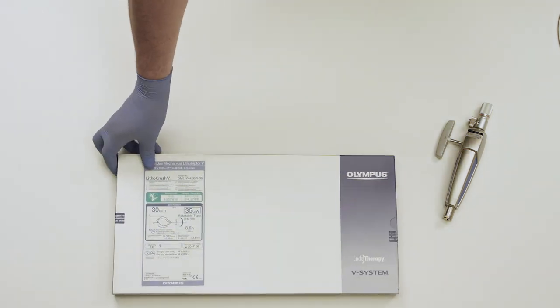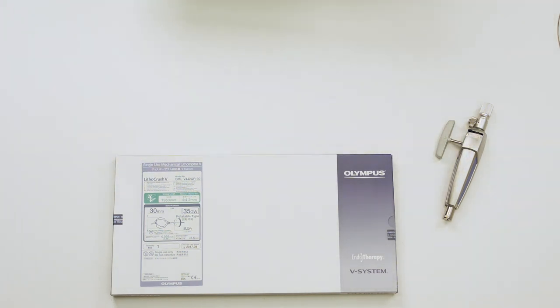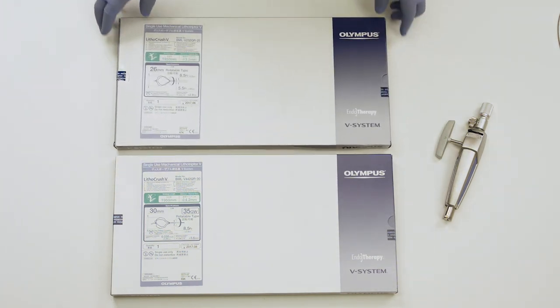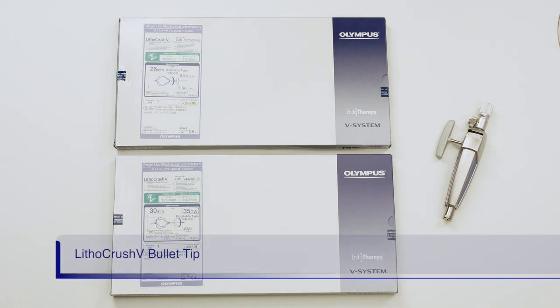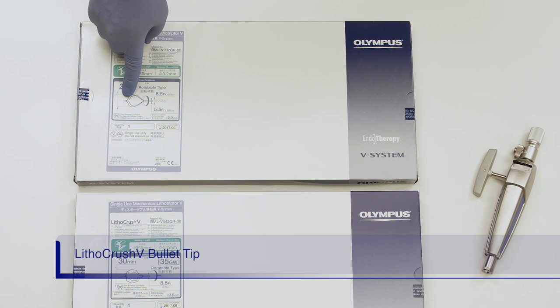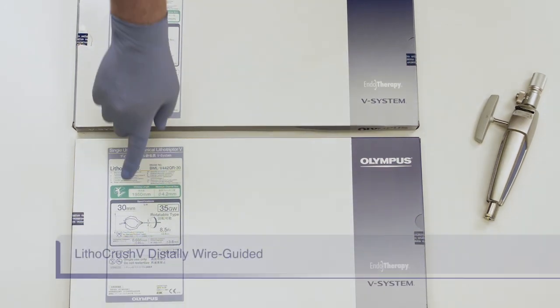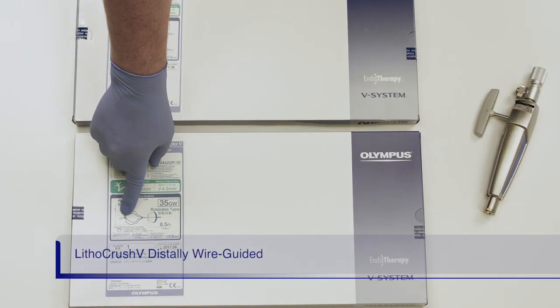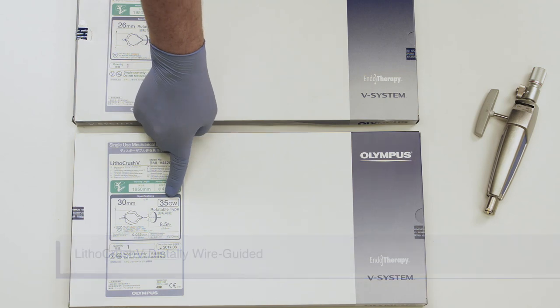Let's review the assembly of the LithoCrush V mechanical lithotriptor. There are two different versions of LithoCrush V. One is the distally wire-guided version. The other is the rotatable bullet tip version. Be certain of which version you have by looking on the box, which will indicate either bullet tip or distally wire-guided. On the distally wire-guided version, there is an indicator for compatible guide wire size.